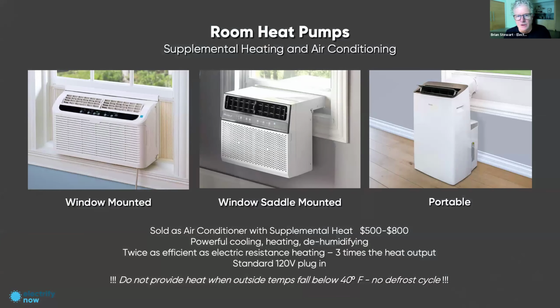There are two classifications of them. The lower cost ones are really only good for supplemental heat, meaning they'll give you great cooling, but only provide heat down to about 40 degrees outdoor temperature, maybe 38, maybe a bit lower. They basically don't work once it gets really cold because they don't have defrost cycles and the other things cold climate heat pumps have. But for shoulder seasons, or if you live in an area that doesn't often get below 40 degrees, these can provide plenty of heat for a single room, maybe even a couple rooms if there's good connectivity between them.